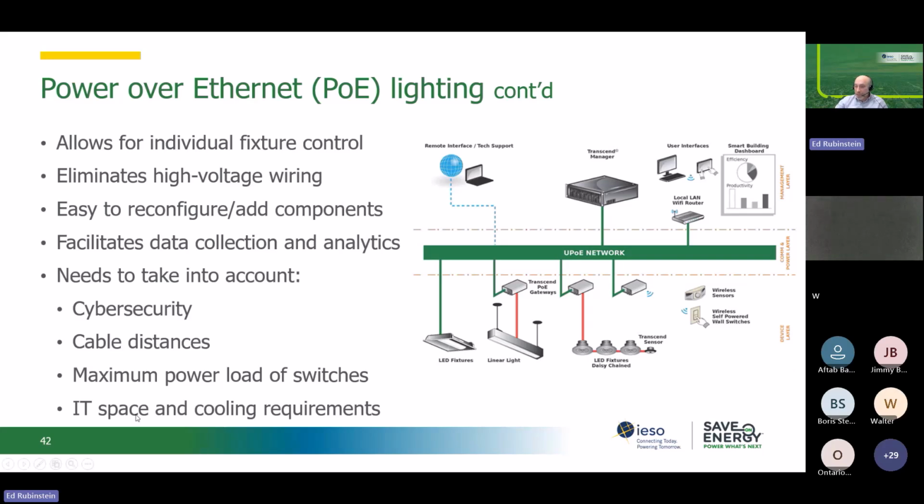What I saw really was this bottom bullet point here, that the cooling requirements, right? So we looked at doing some of these as a retrofit for an area, and there just wasn't enough space in the IT closet to add the extra equipment. But more importantly, these closets, I was in healthcare where more and more IT is being involved. They're already at their maximum for providing cooling to the IT equipment. That IT equipment was there for running computers, running diagnostic imaging equipment, things like that. I would have loved to do some of this, but there was not enough cooling. So had to back away from that.